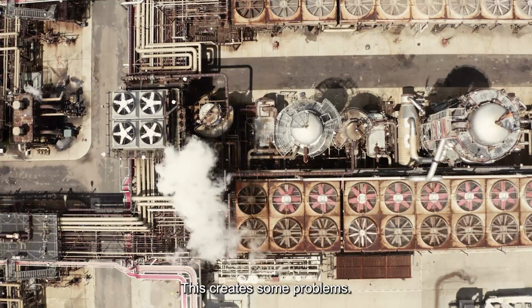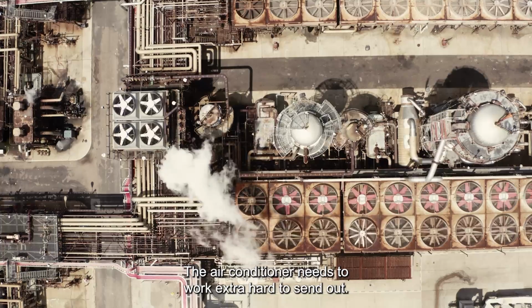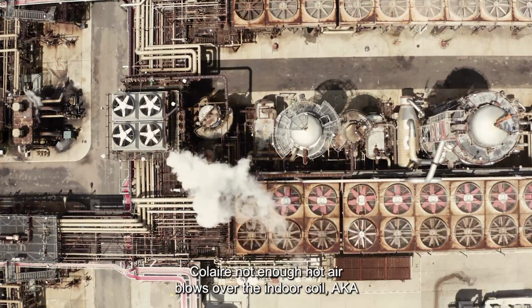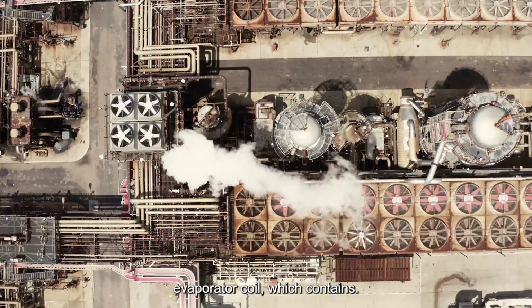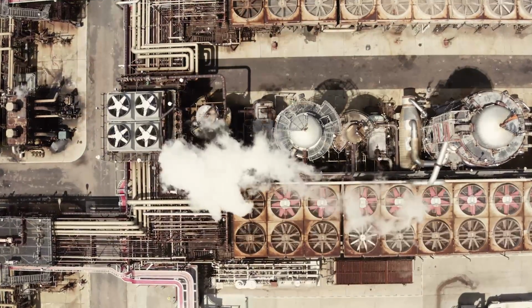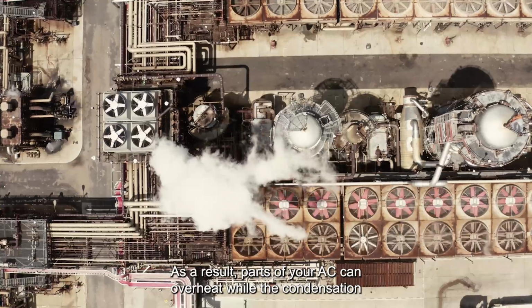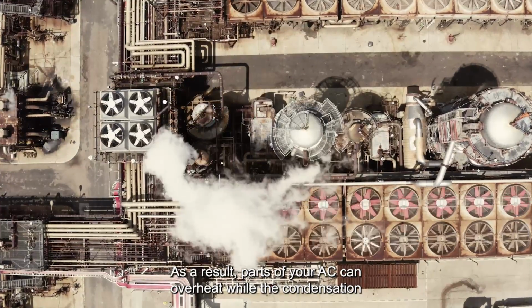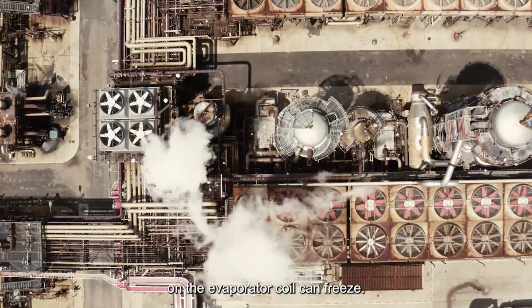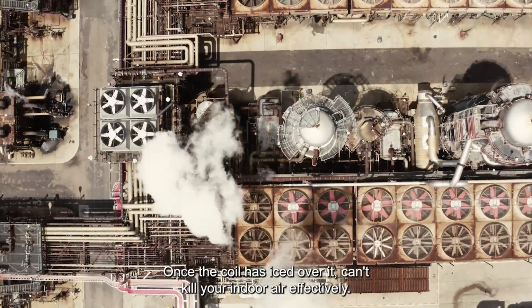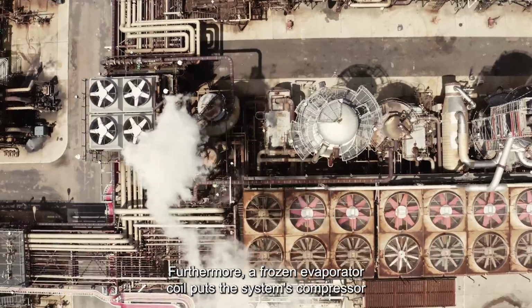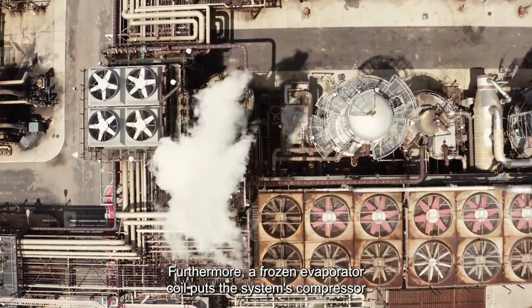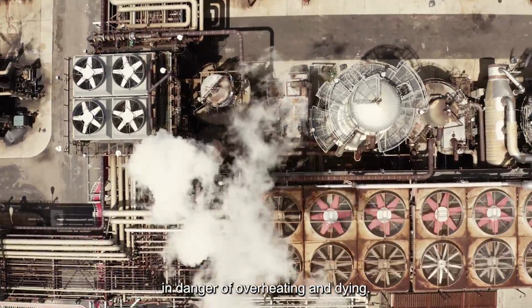This creates some problems. The air conditioner needs to work extra hard to send out cool air. Not enough hot air blows over the indoor coil, aka evaporator coil, which contains refrigerant. As a result, parts of your AC can overheat, while the condensation on the evaporator coil can freeze. Once the coil has iced over, it can't cool your indoor air effectively. Furthermore, a frozen evaporator coil puts the system's compressor in danger of overheating and dying.